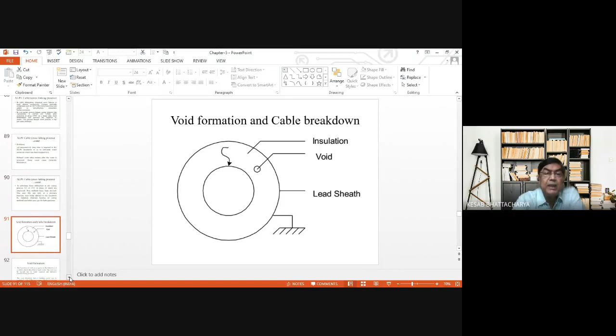The insulating material will try to contract. But the insulating material and the outer sheath do not expand and contract in the same way. It may so happen that the insulating material contracts more than the lead or outside cover. If that happens, then within the insulating material a void will be formed because of non-uniform contraction of the insulating material and the sheath material or covering material. So in this way a void is formed inside the cable, which has been discussed in this slide. We just go through these two points quickly.